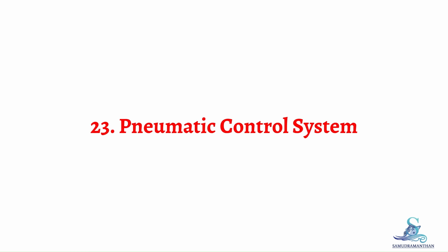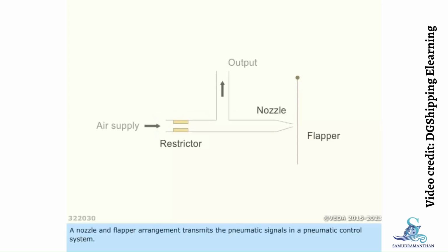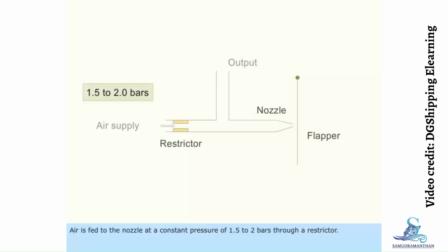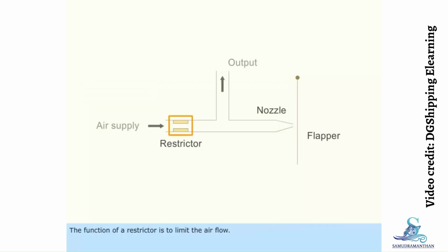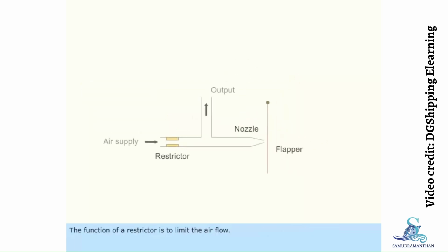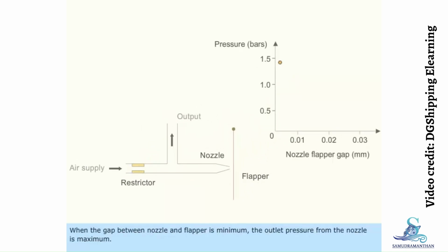Topic 23. Pneumatic control system. A nozzle and flapper arrangement transmits the pneumatic signals in a pneumatic control system. Air is fed to the nozzle at a constant pressure of 1.5 to 2 bars through a restrictor. The function of a restrictor is to limit the airflow. When the gap between nozzle and flapper is minimum, the outlet pressure from the nozzle is maximum. When the gap between nozzle and flapper is maximum, the outlet pressure from the nozzle is almost equal to the atmospheric pressure.